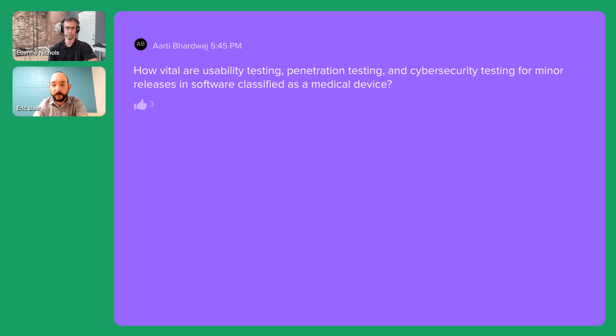If you're adding functionality, then they're more focused on things like your full design control process with all your regression analysis and everything else for whatever functionality you're adding. And as for usability testing, that gets into IEC 62366 questions of, well, what critical tasks have you impacted? Have you impacted them in such a way that the risk profile of those critical tasks has changed? And well, now you need to do some sort of formative test to prove that you haven't changed that usability model in any particular way. So like I said, it's a loaded question. There's a lot of answers to a lot of different variations on that question.